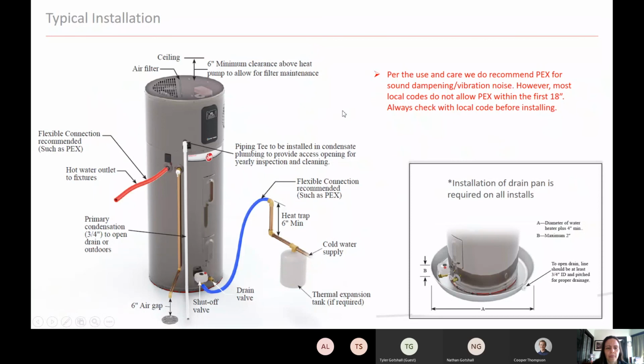So we'll go back really quick. Something to note, if you look into the use and care manual, we say that you can utilize PEX right here for that first part of the connection. And the reason we recommend the PEX is for sound dampening and vibration noise. So for some people, they might get some vibration. It might play up the harmonics of the house. But to code, there are many places that local code says you can't use PEX within the first 18 inches. So what we say is check with your local code. If you're allowed to use the PEX, use it. If not, go with your hard piping, but just be aware of the fact that you will get a little bit better sound dampening capabilities if you utilize the PEX for those first 18 inches.